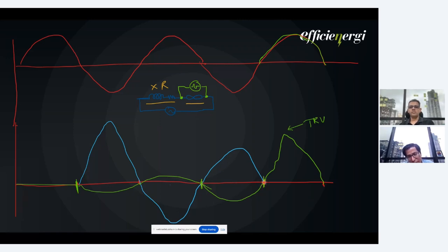And after the complete extinction of the arc, there is a sudden rise in the voltage across the fuse because the fuse gets open. This is what we call the TRV, transient recovery voltage. Again, TRV is a very important topic that we'll cover in the short circuit webinar. So here, this particular time will be the melting time. This time will be the arcing time. And this complete period is the operating time of the fuse.